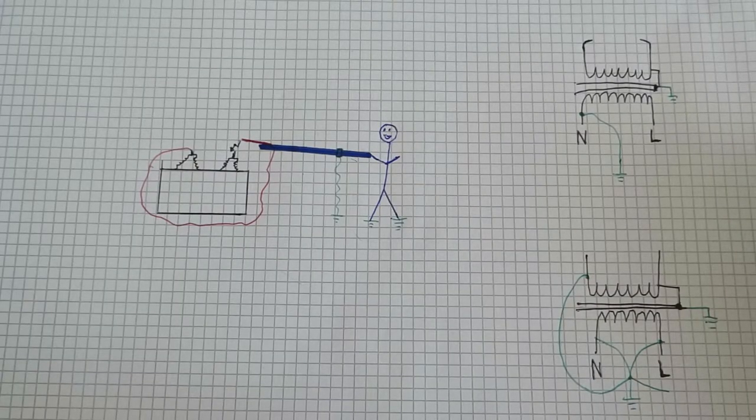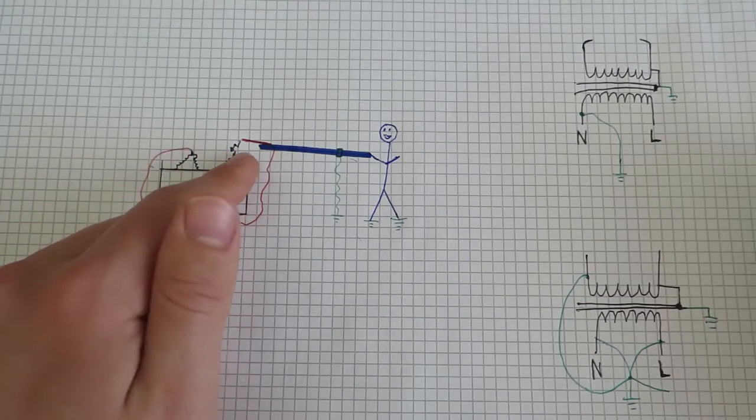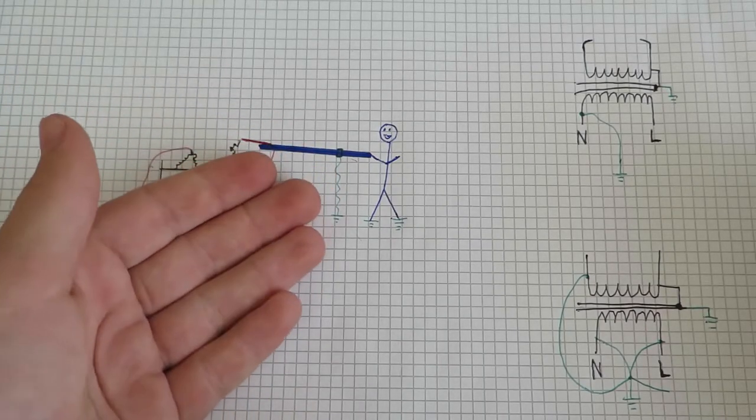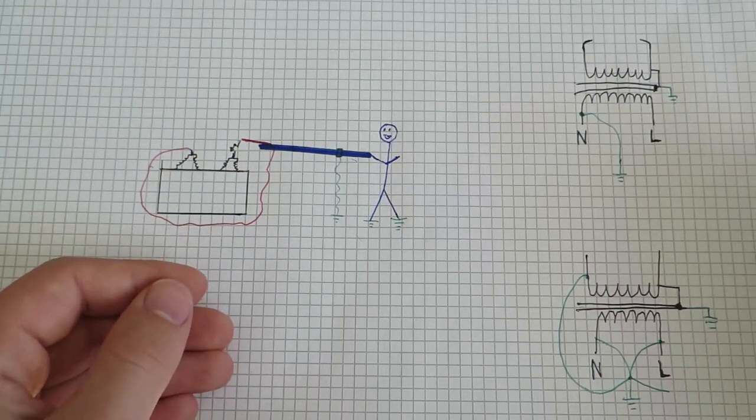Whenever possible in the realm of high voltage, you should always ground the end of your high voltage arcing stick. So that if the stick conducts for some reason, you're gonna be safe and you won't get the shock. But in some cases, like for example with neon sign transformers or at very high voltages with x-ray transformers and stuff, that is not possible.